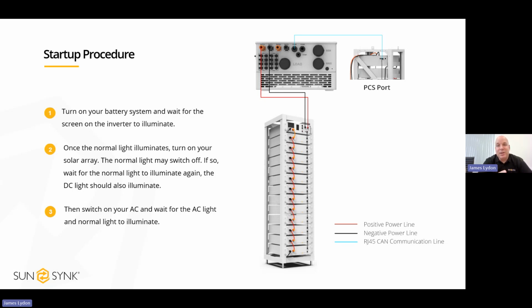And what that is doing is, rather than turning everything on at once, if there's going to be an issue with comms, typically it's between the inverter and the batteries. So by introducing the batteries first, it lets you make sure the comms with the batteries are good. When the screen comes on, when you go into the settings, the bottom right setting, it will say LIBMS. If you click on that, and if you see positive values on there, so if it's showing you the battery voltages and the temperature of the batteries, you've got good comms. If you click on that screen and you've got a load of zeros, there's an issue with the comms.